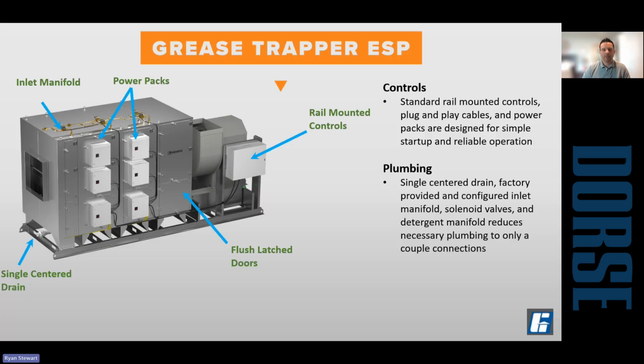In a perfect world, we put it together from the factory. So it's all factory assembled. You'll have your wash manifold put together, the drain put together. You can have the control cabinet mounted onto the rails. Everything's factory wired. The reality is these things are huge. And a lot of times it's difficult to get these into a building in one section. So they can be shipped in individual pieces. The electrostatic ones, since they have a wash system, they need to be welded back together continuous. So it's a pretty extensive process to put them together in the field. The filtration one is listed to be bolted together. It doesn't have a wash system. And so they've been able to get a listing for that.